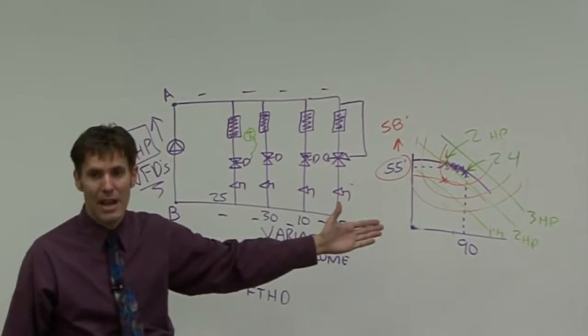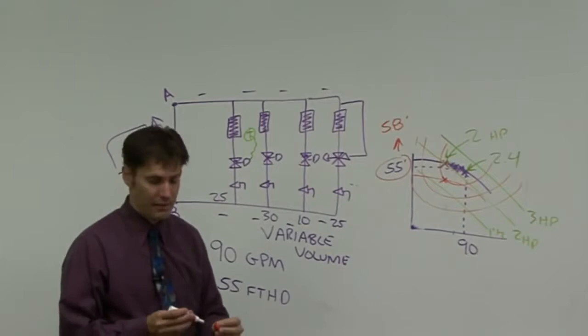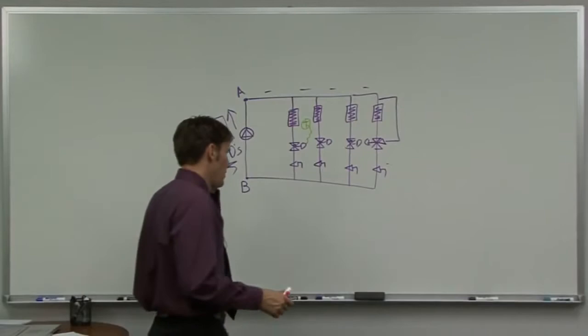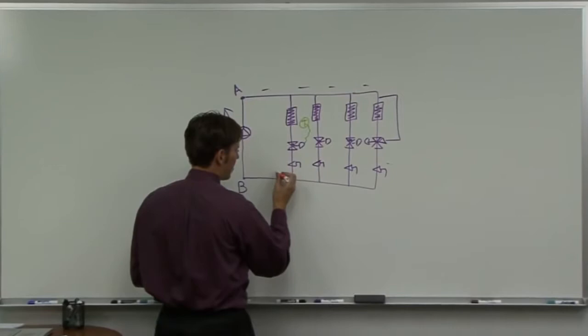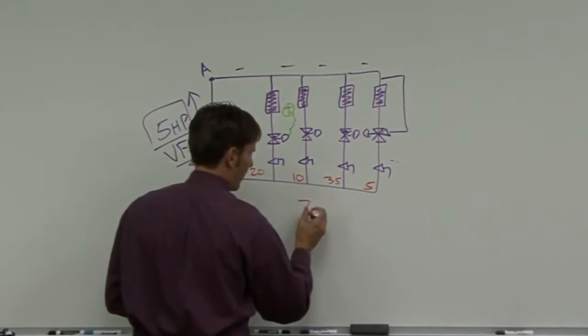You have to make sure the system is operating properly so that we can get the greatest turndown on that VFD. Let's get into balancing the system. Consider a system where: circuit 1 wants 20 GPM, circuit 2 wants 10 GPM, circuit 3 wants 35 GPM, and circuit 4 wants 5 GPM. That totals 70 GPM — that's what my system requires at design conditions, say 0°F outside air temperature.